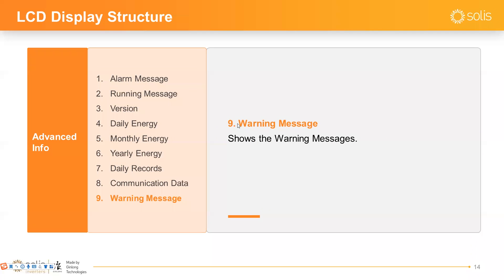The difference between Alarm Message and Warning Message: Alarm Messages affect normal generation and will stop the inverter. Warning Messages only give a notification — for example, high temperature or a surge event — and do not affect normal generation.